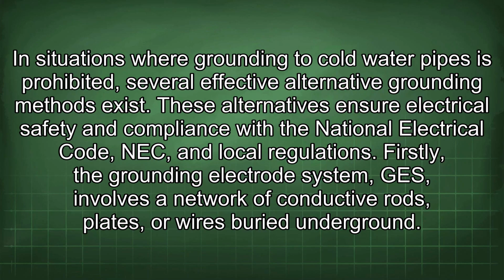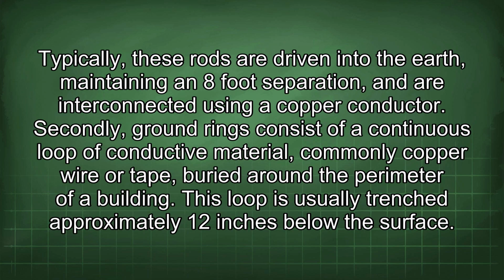In situations where grounding to cold water pipes is prohibited, several effective alternative grounding methods exist. These alternatives ensure electrical safety in compliance with the National Electrical Code (NEC) and local regulations. Firstly, the grounding electrode system (GES) involves a network of conductive rods, plates, or wires buried underground. Typically, these rods are driven into the earth, maintaining an 8-foot separation, and are interconnected using a copper conductor.